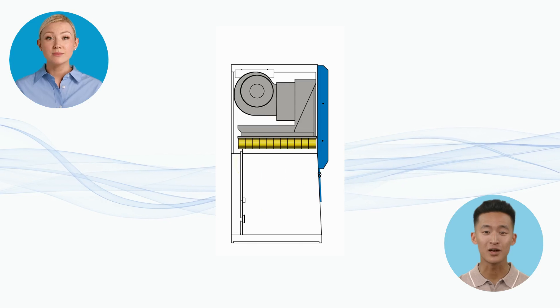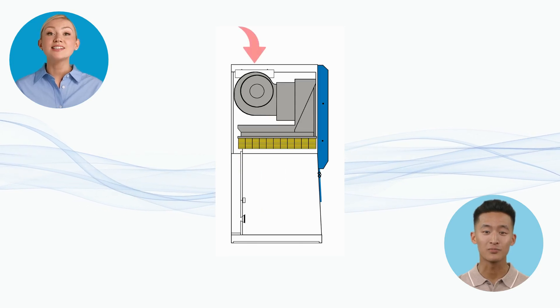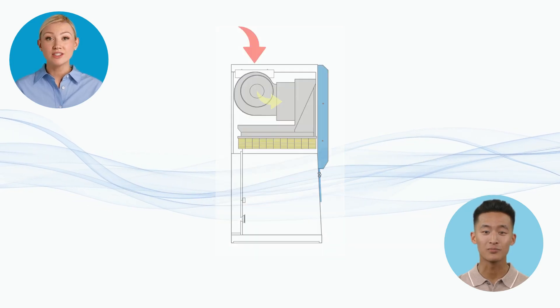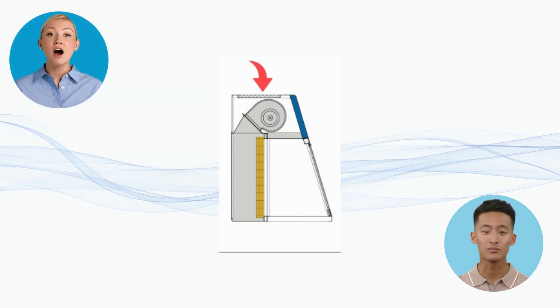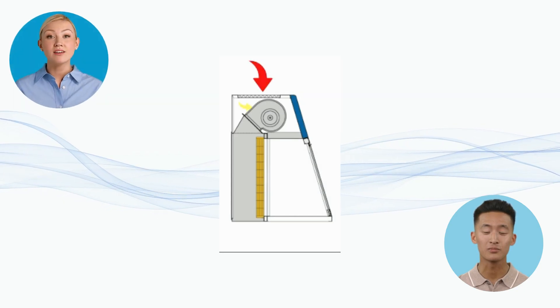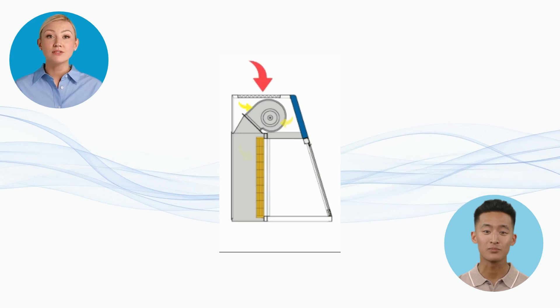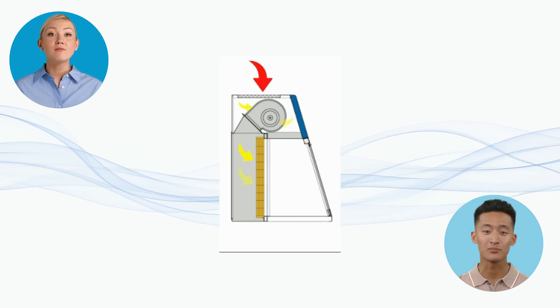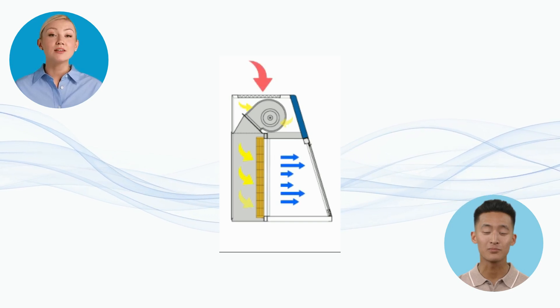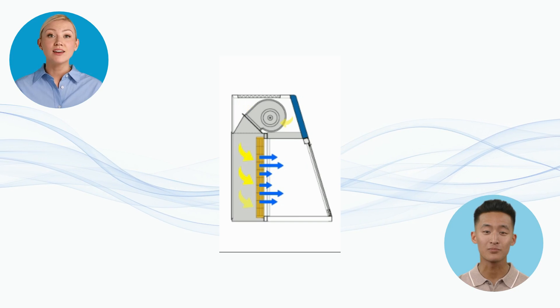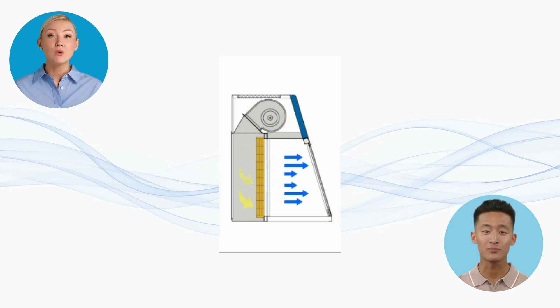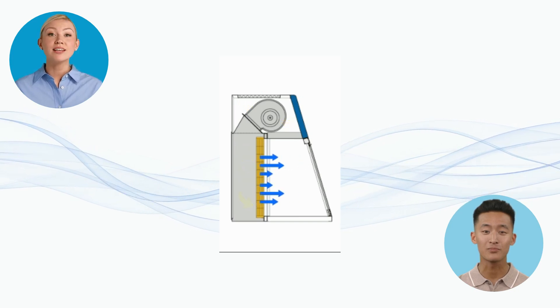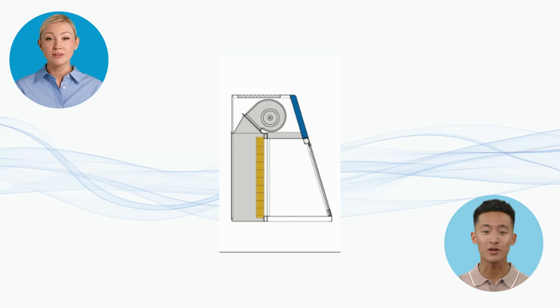That's great. And horizontal? Well, let's do the same for that version. So, we've now sliced the horizontal flow hood in half. Again, the red arrow shows where air is drawn in from the top. It then passes through a pre-filter and a HEPA filter at the back of the unit, and then flows horizontally across the work area before being exhausted out the front opening.